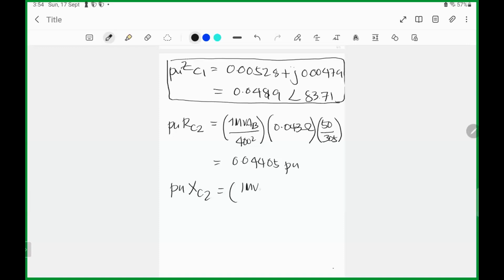Then PU, the reactance of cable 2, 1 MVA base 400 squared times 0.039 ohms times 50 divided by 305 meters. The answer is 0.03995.